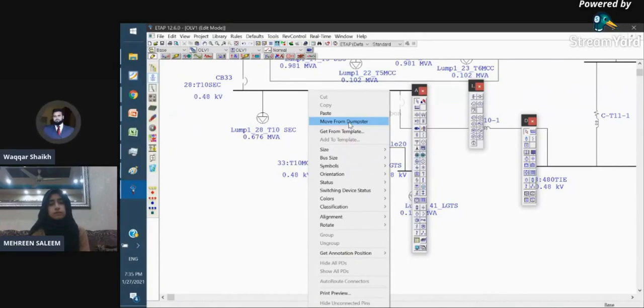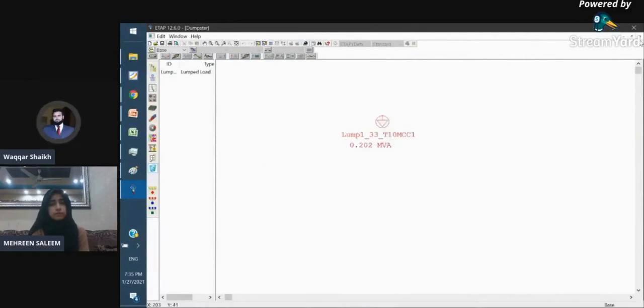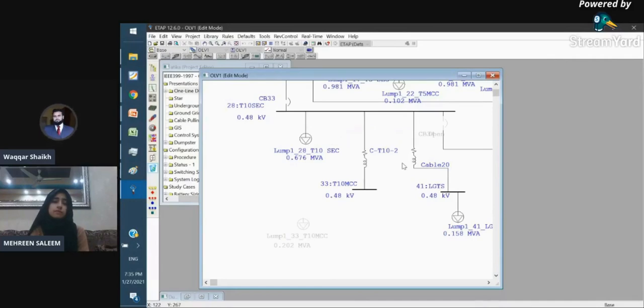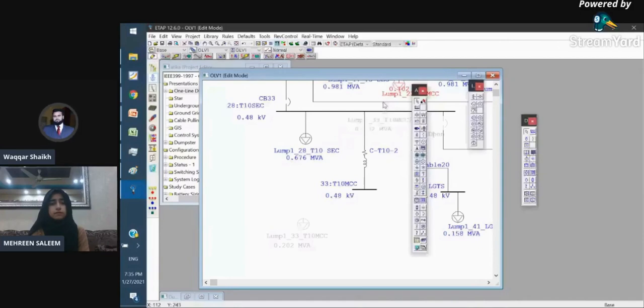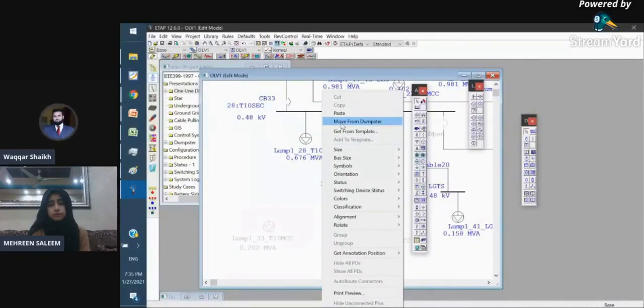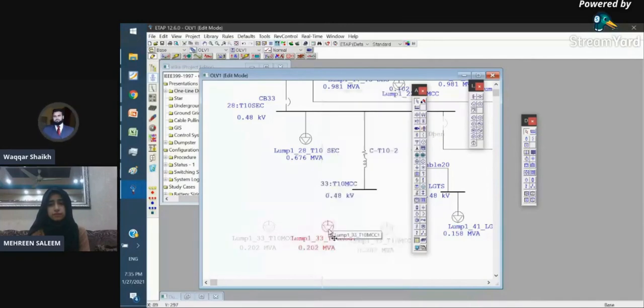Also, if you are copying this, it will create a copy of it with another tag number in the dumpster. You can see now this is T10MCC1. So if I say paste, it will not bring back T10MCC1; it may bring T10MCC2, because I am not bringing it back from the dumpster, I'm just saying paste. So it brings T10MCC2, meaning one serial number or sequence item is missed out. It means it is not the same component you copied; it has created a new component in the dumpster, a separate copy. So in order to bring it back properly, you have to use move from dumpster. This is MCC1, which when you copied it, went into the dumpster as a copy of the first component, and when you said move from dumpster, it was back in the main window.